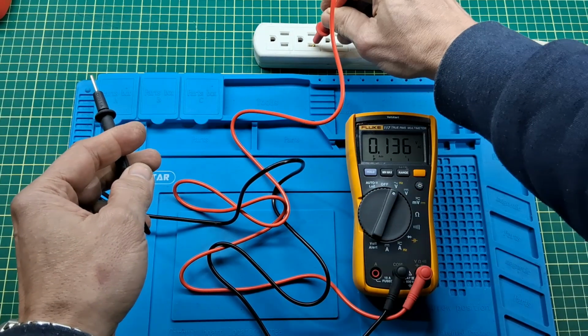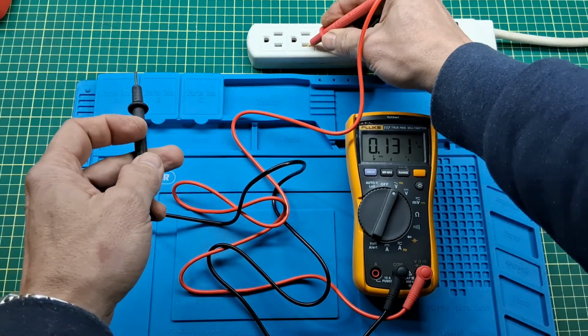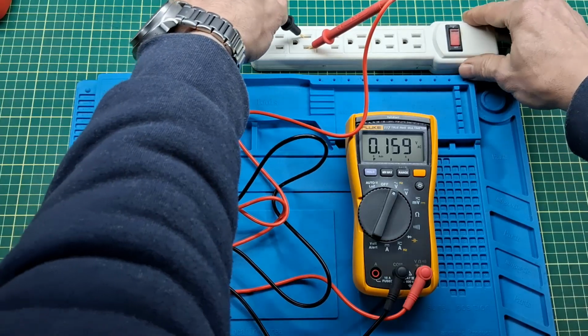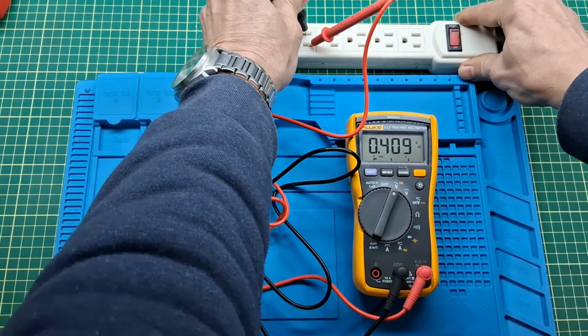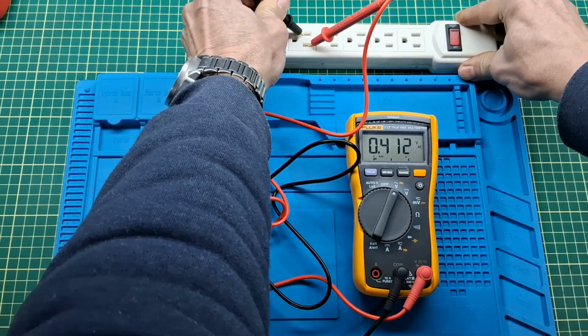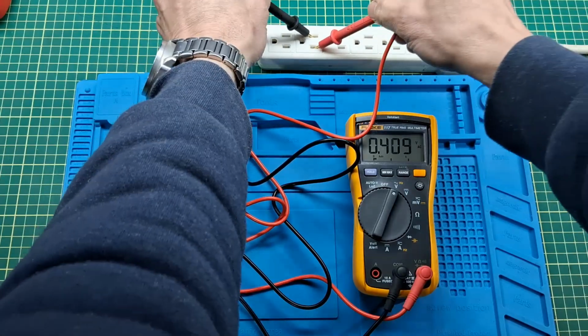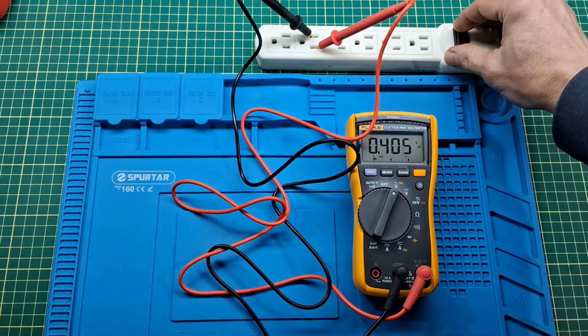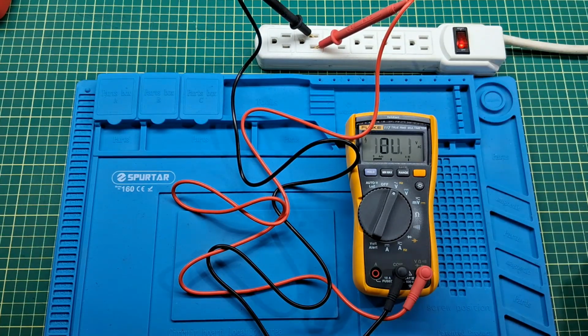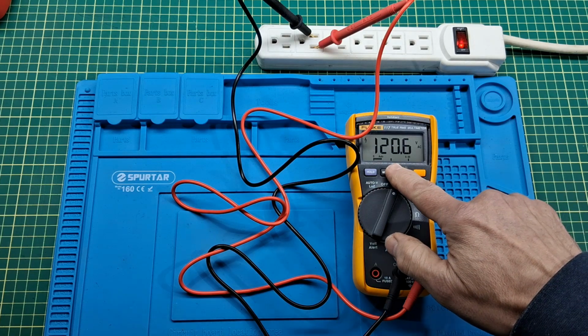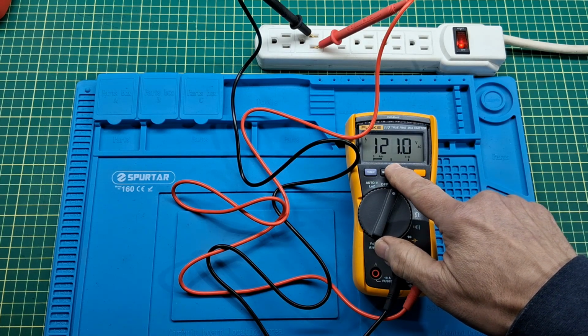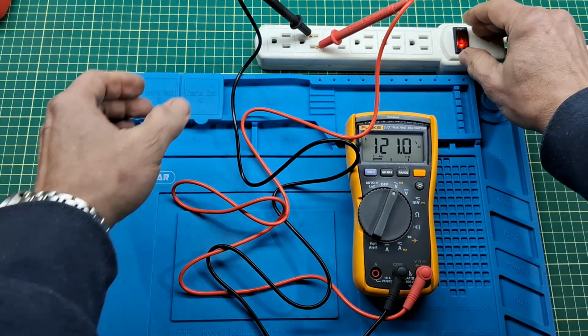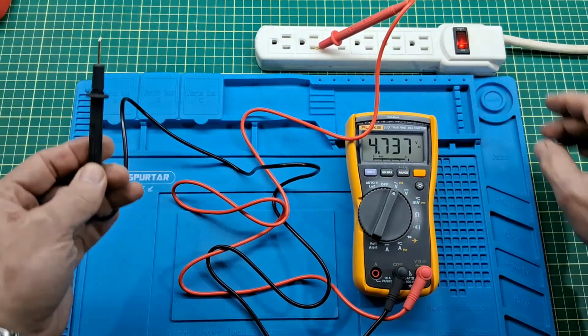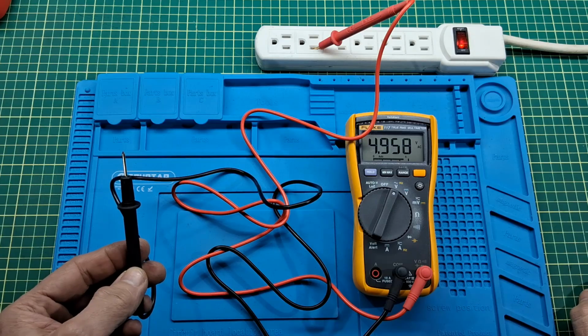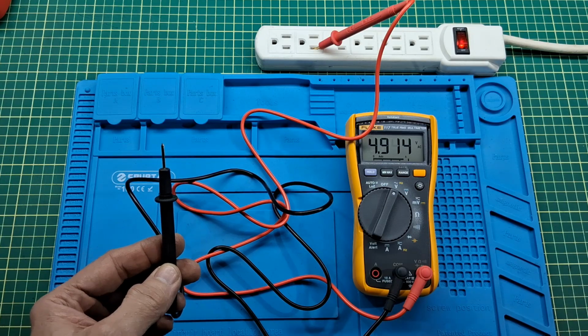With the power bar switch in the off position, I plug the red probe into the hot outlet, black to neutral, making sure we have good connection. Power on: over 120 volts present. Now I remove the black probe. The red stays plugged in and the power bar is energized.